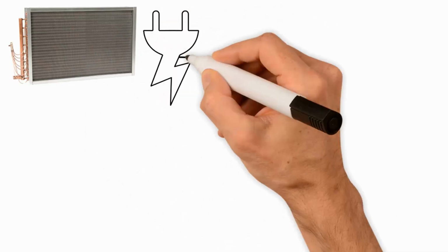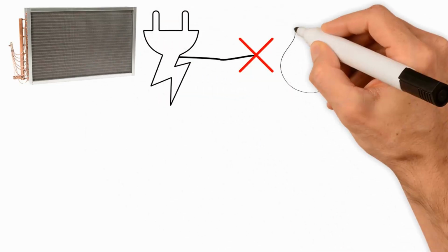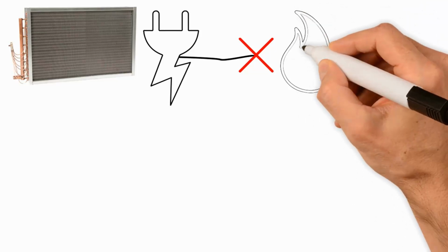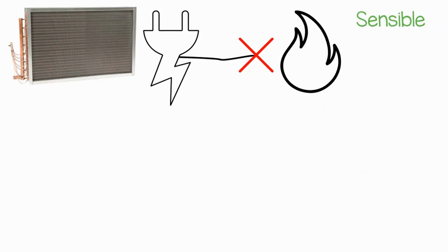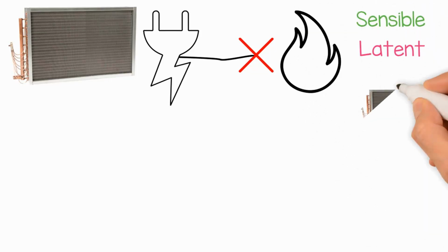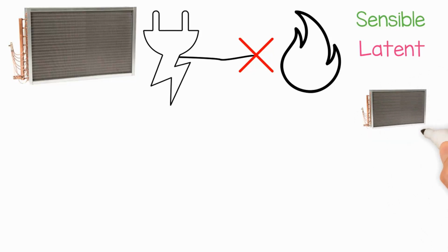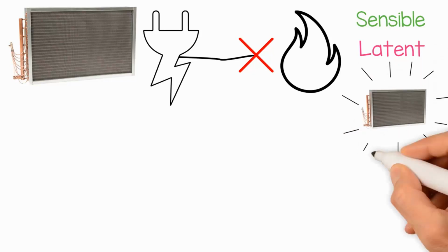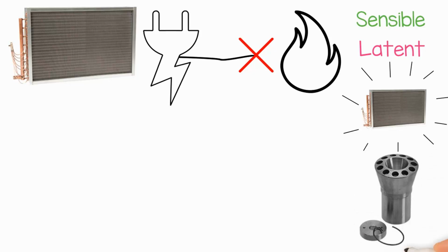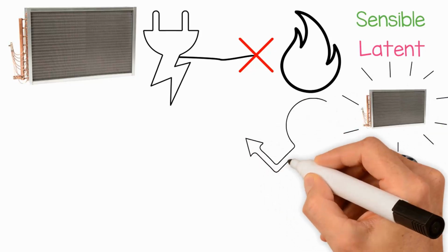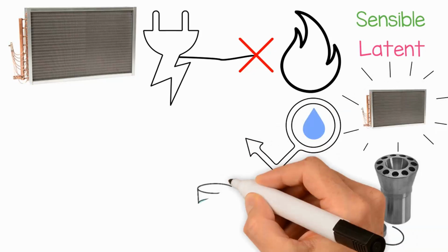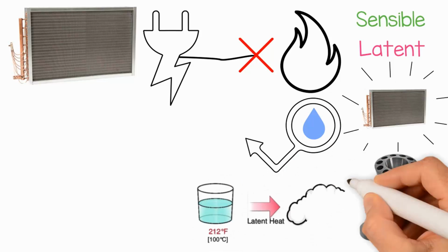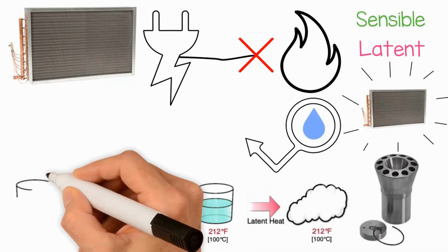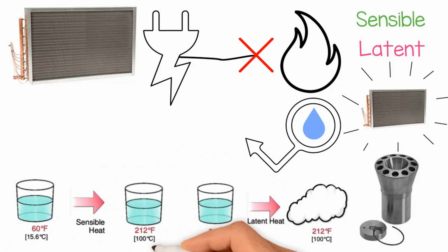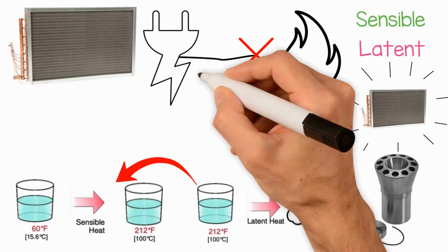This is where your energy is absorbed or rejected. Let's assume we both know that there are 2 forms of heat energy, that is sensible and latent. So with this new range of heat exchangers that we have developed, we've got a wider distribution of refrigerant to create a better saturated condition to the whole of the coil, thereby increasing the amount of latent heat energy being absorbed, as we know that latent heat is quite difficult to remove compared to sensible heat.